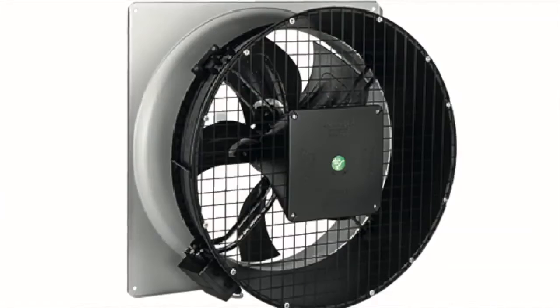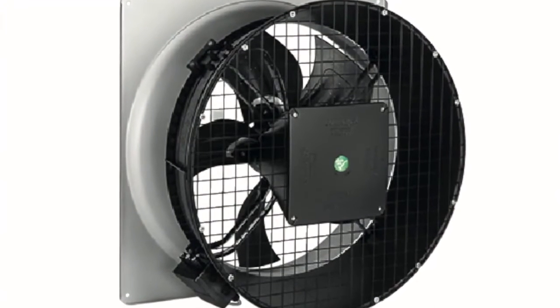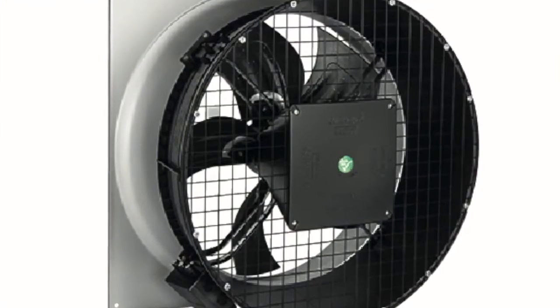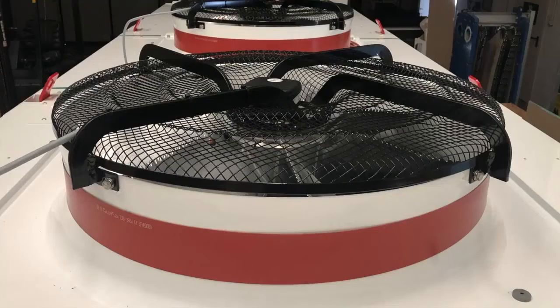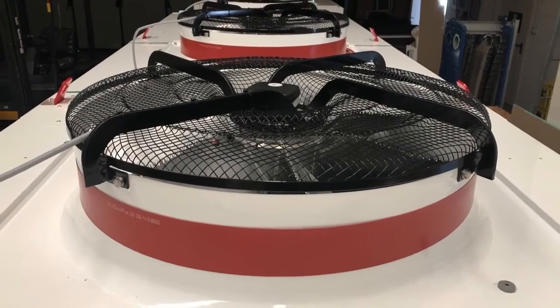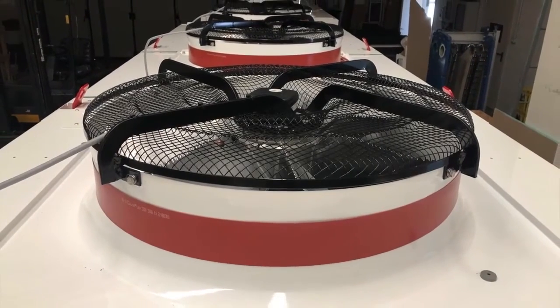On these machines, fan technology has been greatly developed, both to limit the noise, since they are machines that are typically installed on roofs, in outdoor areas, and therefore with easy noise diffusion, and from an energy point of view, by seeking out highly efficient fans in order to minimize energy consumption as much as possible. The maximum performance is achieved by using fans with electronically controlled motors, the classic EC motors. Why do we do a speed check based on environmental conditions?